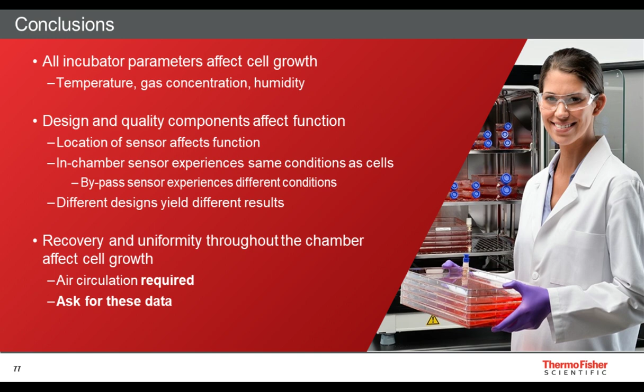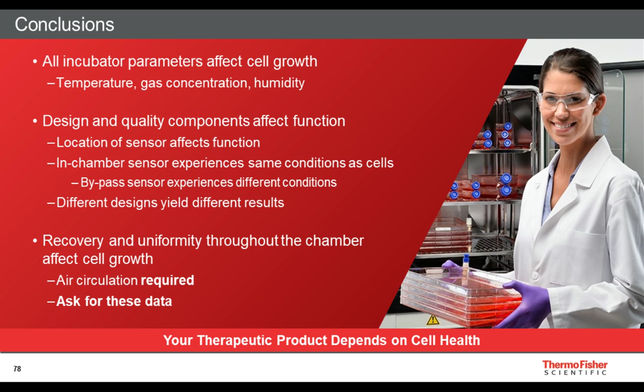So recovery after a door opening and uniformity throughout the incubator chamber, again, affect the cell growth. And so air circulation with a circulating fan is required for uniformity and fast recovery. And you can ask for these data from the manufacturers. If you're looking at, for example, initiating a new institute, a new building, you're expanding your processes, and you're thinking about a large incubator purchase, don't just look at a list of specifications, but ask for these data, and even consider buying a single incubator from a few different manufacturers to compare how that incubator performs in your processes, because your end product depends on the cell health, and the cell health is dependent on the CO₂ incubator.